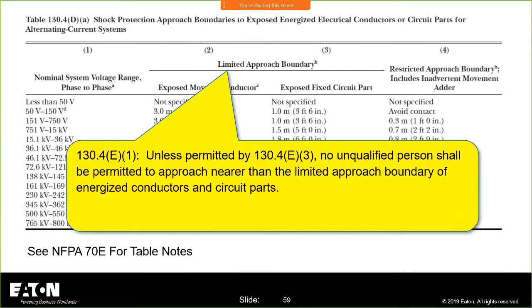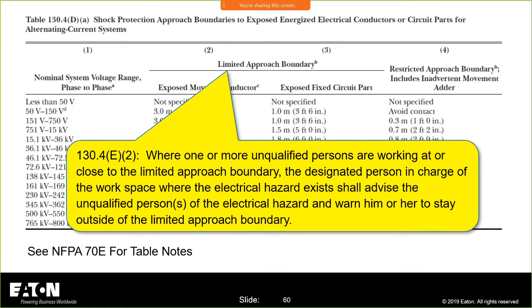But you have the limited approach boundary that tells us that no unqualified person can be permitted to approach nearer than what we see in these distances. So this was one of our questions that I took out of this table, basically. It tells us that if we do have an unqualified person there, you have to have a qualified person or somebody in charge to advise that person of what they're being exposed to. You're coming into an area where you are close enough that you could possibly come in contact with something that is energized, and you're going to have to educate that person and watch that person closely.